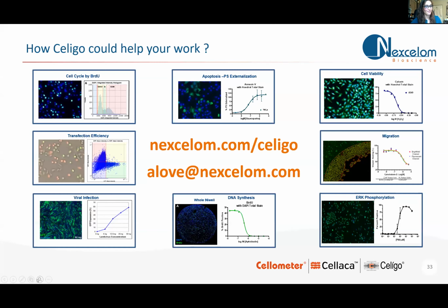So Svetlana Mazel is asking, how sensitive is the Celigo for the single cell deposition? That's a great question. So efficiency, if you're using a fluorescent tracker dye, such as a calcein AM or a CMFDA, or if your cells are already fluorescent protein expressed, is 99% or greater. If you're using bright field only, you can't exclude things like media artifacts and artifacts on the plastics themselves.